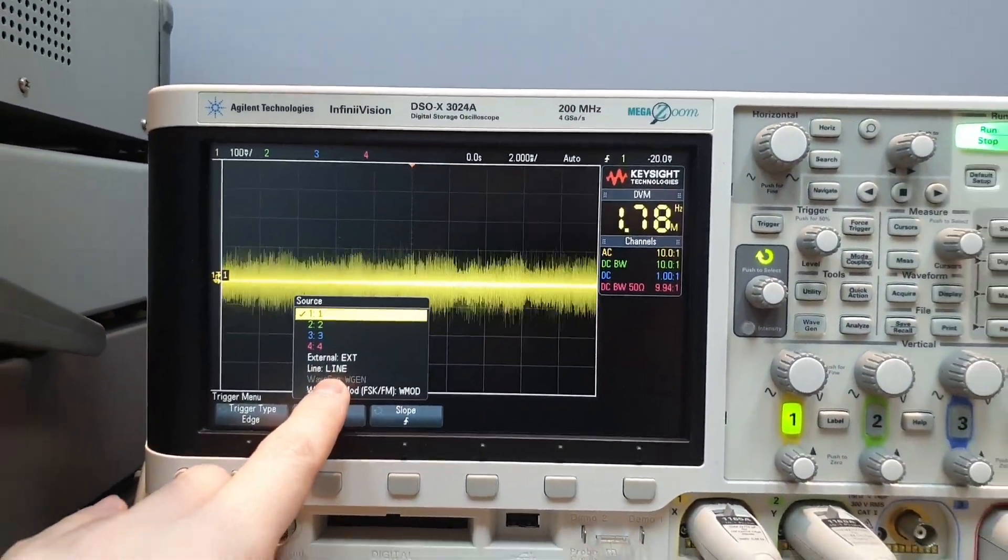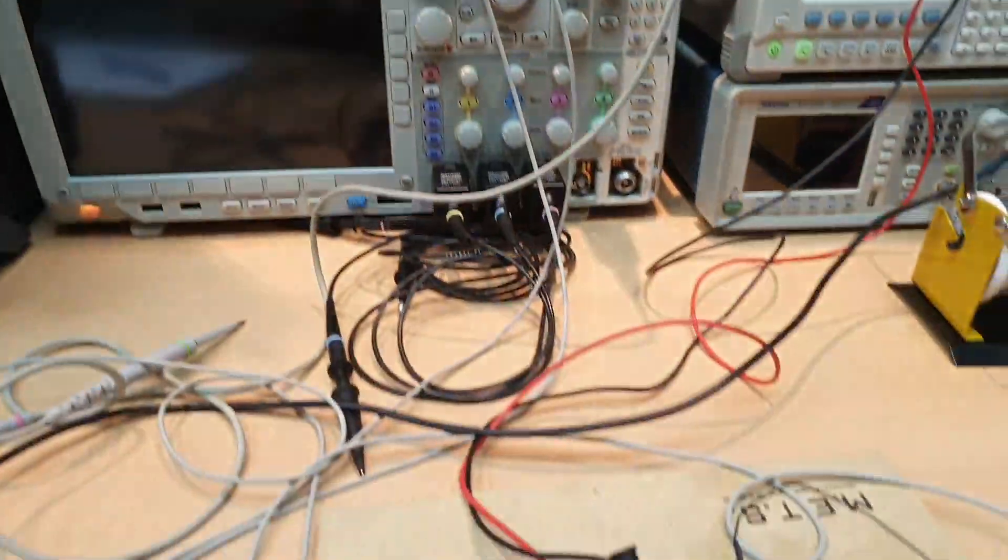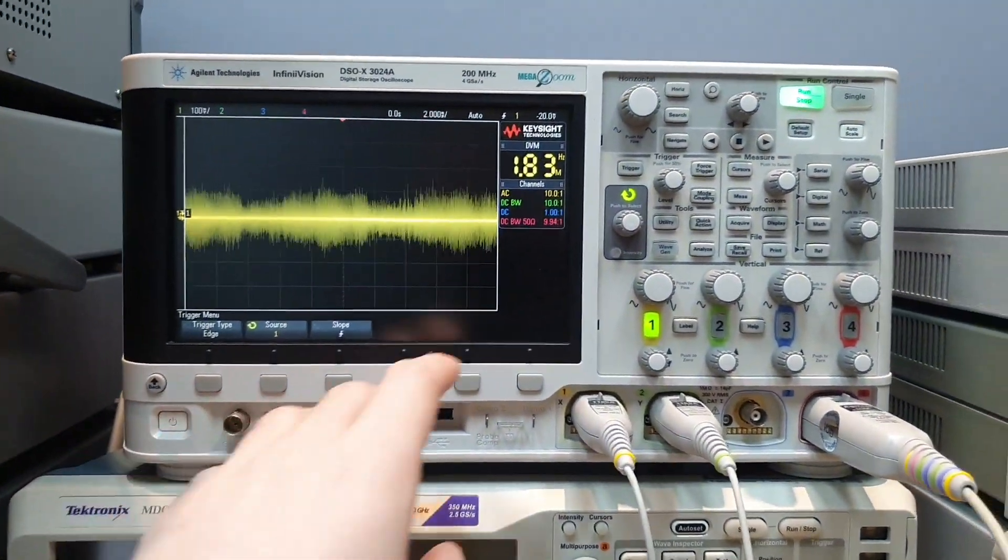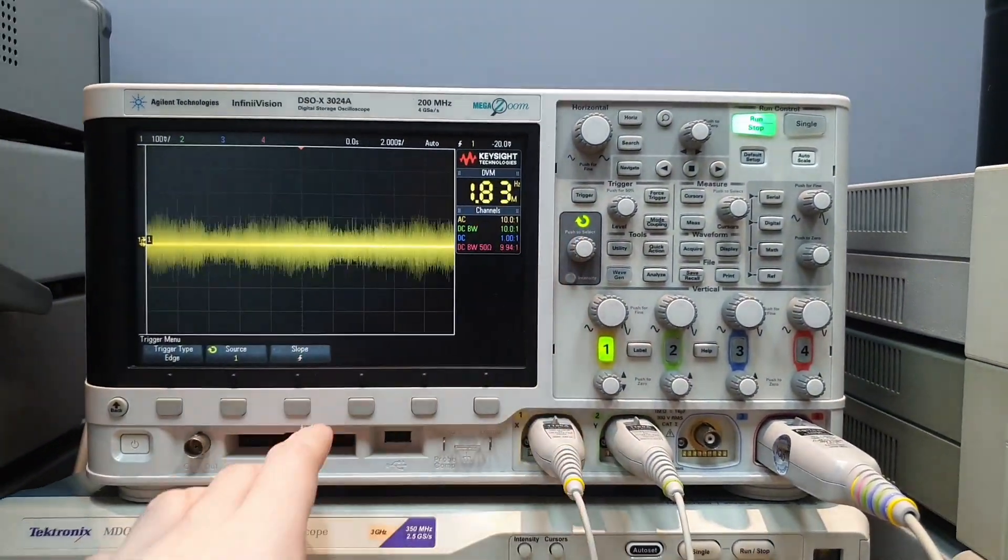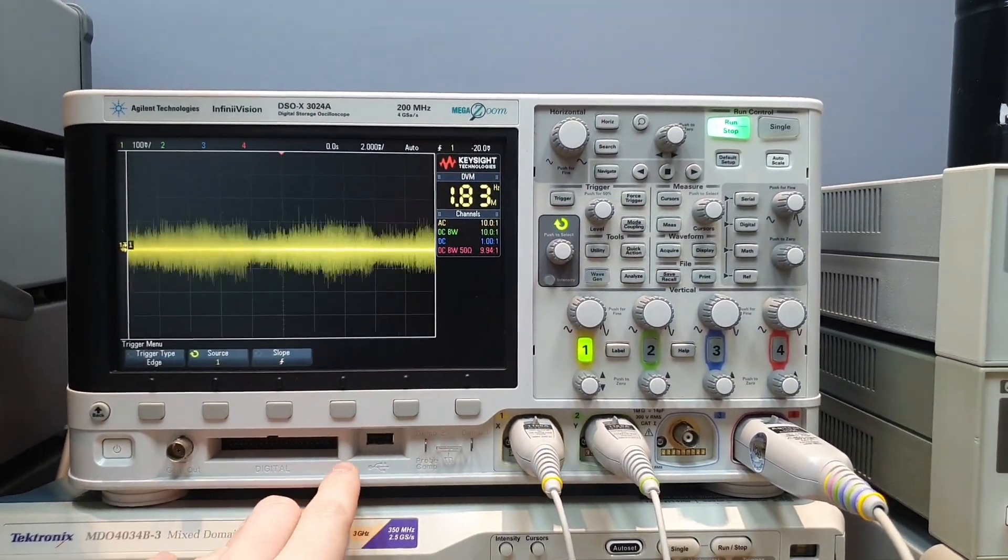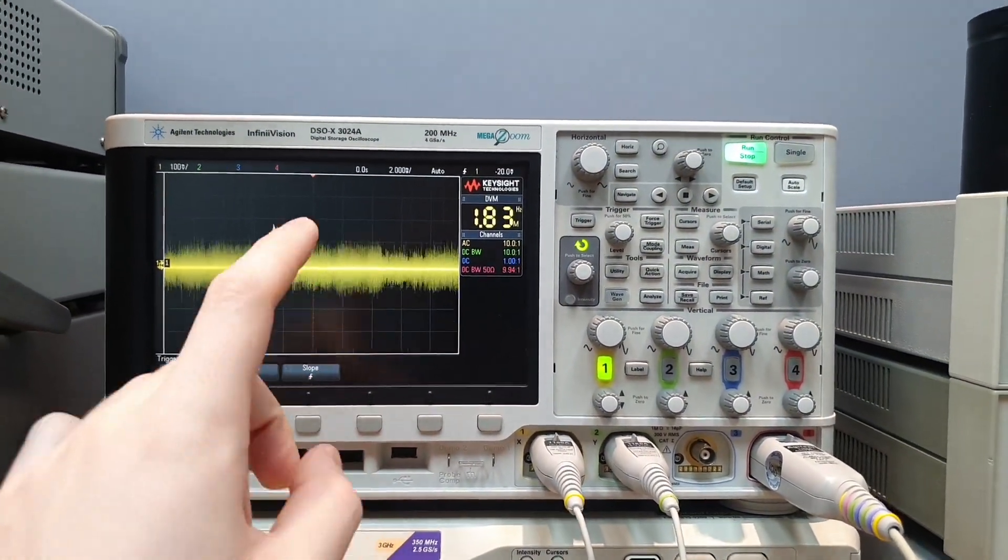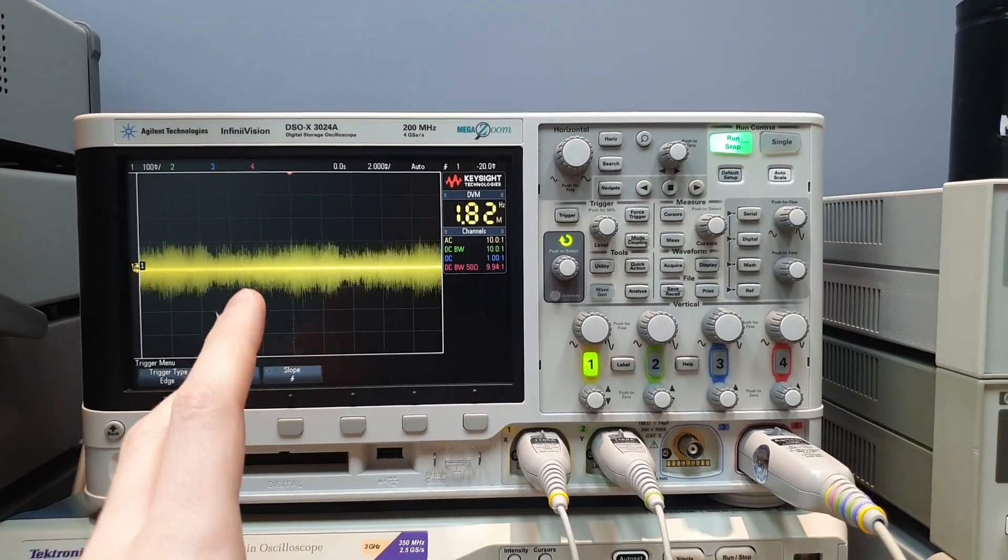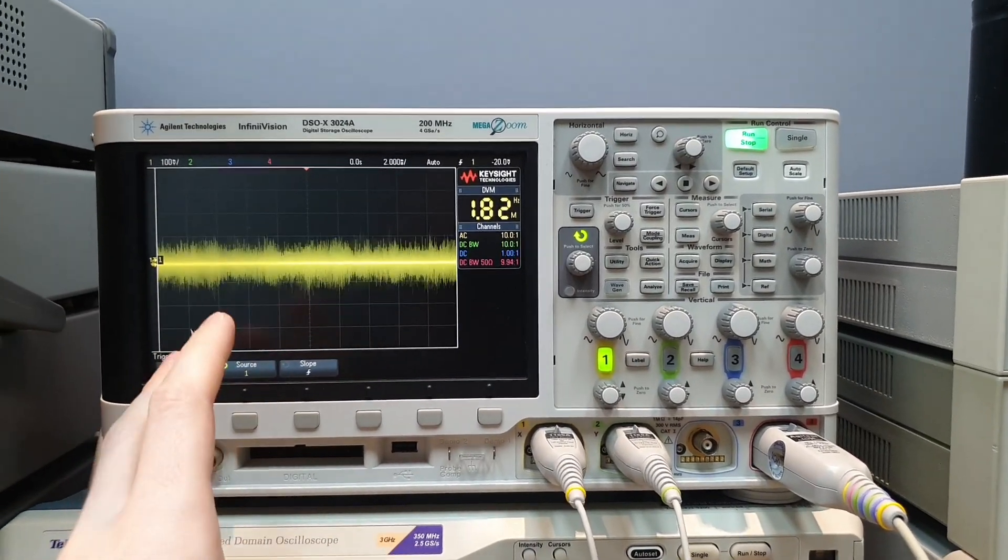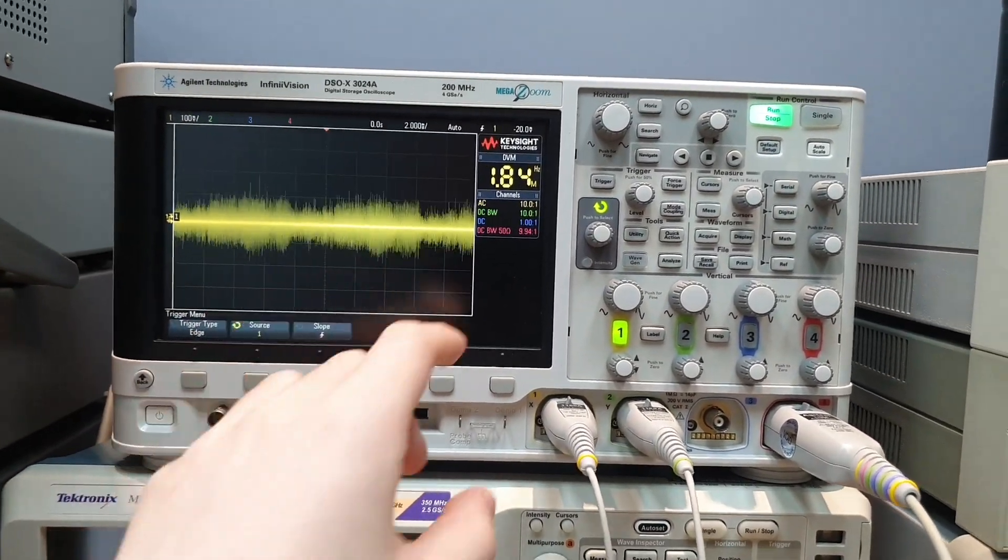So we can try to trigger the noise correlating with the line frequency to see if the noise comes from line.